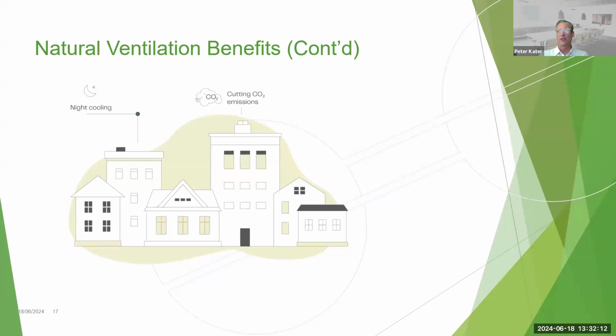You can obviously get the reduced CO2 emissions associated with not having the mechanical ventilation operating all the time. You get the safety benefit with smoke and heat evacuation during a fire. By the way, that feature, that benefit, is available with natural ventilation systems. So the natural ventilation system can provide the fire safety benefit as well as all of these other benefits. It can be used for both. So it only functions as a smoke and heat evacuation system when the fire alarm system triggers that operation in the controller. You can have app-based control of the system on your phone, which makes it very convenient for building management staff to control and optimize the operation of the system.